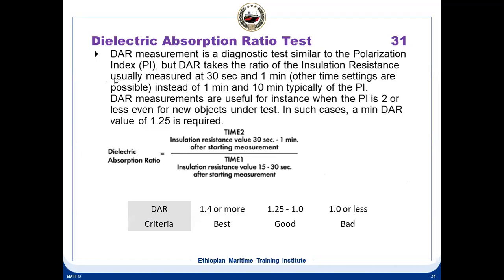Then the other test is called the DAR test, a dielectric absorption ratio test. This test is applied between 30 seconds and 1 minute. The DAR measurement is a diagnostic test similar to the polarization index, but it takes the ratio of insulation resistance measured at 30 seconds and 1 minute. So you can see here the DAR criteria: 1.4 or more is considered best, 1.2 to 1.4 is good, and 1.0 or less is bad.